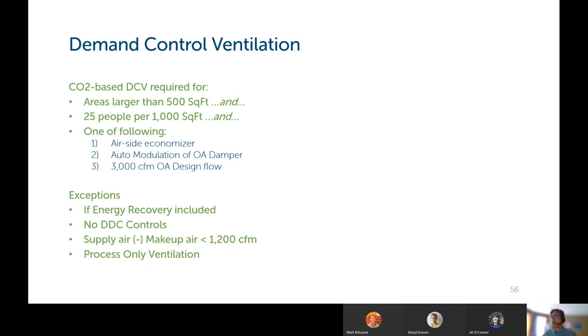And there are exceptions to needing demand control ventilation in a space if that space has energy recovery included, if there's no DDC controls controlling that space, if the supply air subtracted from the makeup air is less than 1200 CFM, you don't need demand control ventilation, or if it is process only ventilation, it's not required.